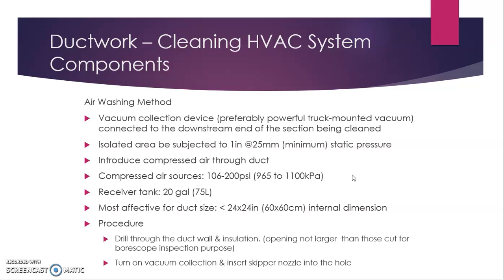In the air washing method, we still use the vacuum collection device, but preferably a powerful truck mounted vacuum. It has very high pressure and is connected to the downstream end, and the vacuum will suck from the downstream. The area must be isolated and subject to about 25 millimeter static pressure. We also introduce compressed air through the duct, so it pushes from one side and sucks from the other side. The compressed air source must be about 106 to 200 psi depending on our ducting system, and the receiver tank about 20 gallon or about 75 liter. This is usually effective for duct sizes below 24 by 24 inch internal dimension. If it is above 24 by 24, we have to look into another method.